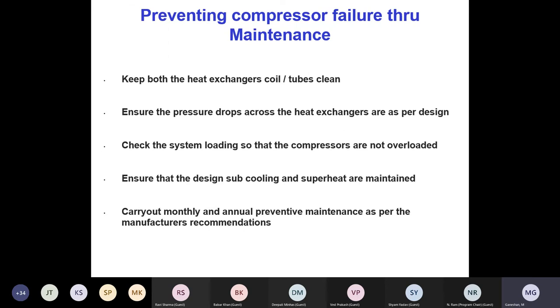Especially check the system loading and unloading, and ensure the design subcooling is maintained, which is very, very important, and superheat is properly maintained, because almost all compressors are cooled by the return suction, especially semi-hermetic compressors. If the return gas is not proper and becomes hot, then naturally the winding will get hot, and naturally the compressor will also be working at a higher load.